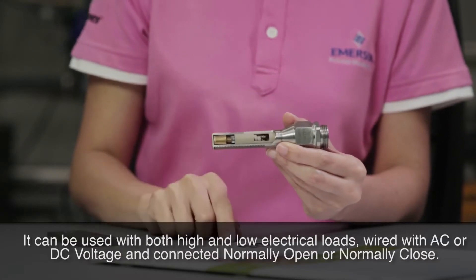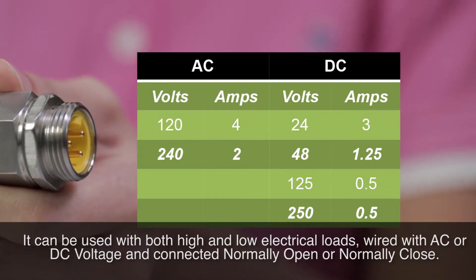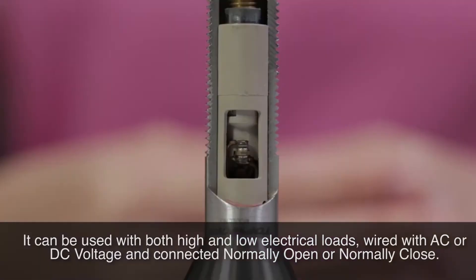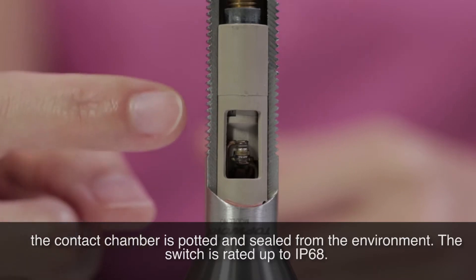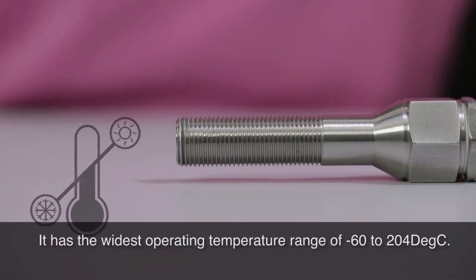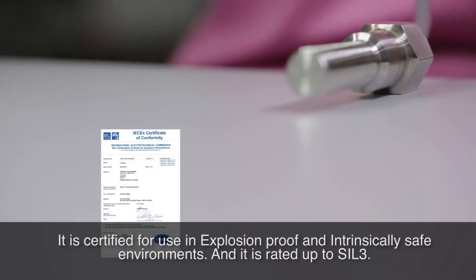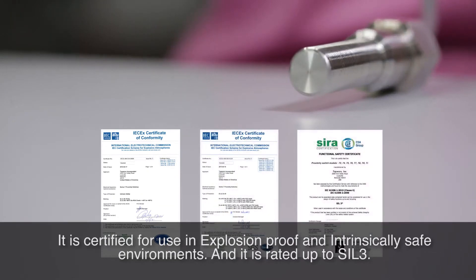It can be used with both high and low electrical loads, wired with AC or DC voltage, and connected normally open or normally closed. GoSwitch is hermetically sealed — the contact chamber is potted and sealed from the environment. The switch is rated up to IP68. It has the widest operating temperature range of minus 60 to 204 degrees Celsius. It is certified for use in explosion proof and intrinsically safe environments, and it is rated up to SIL3.